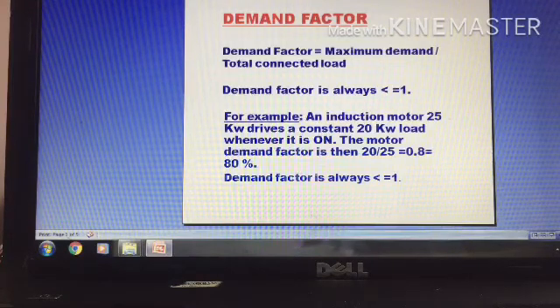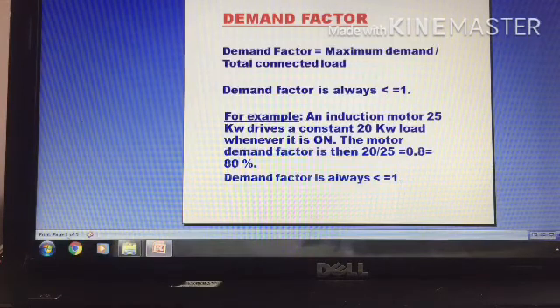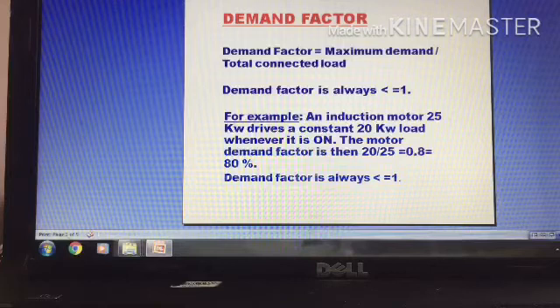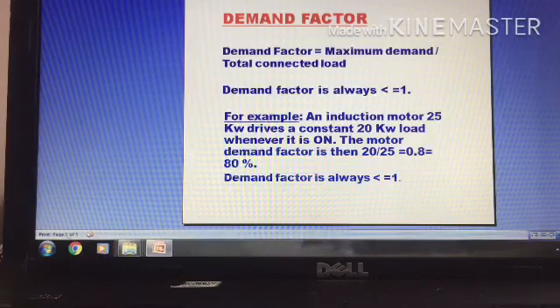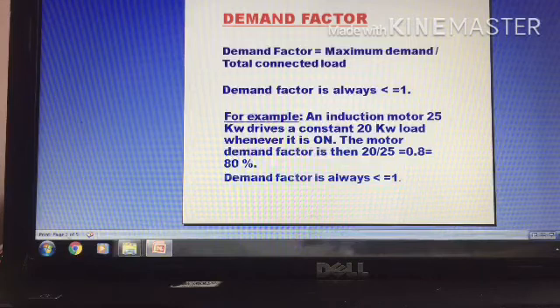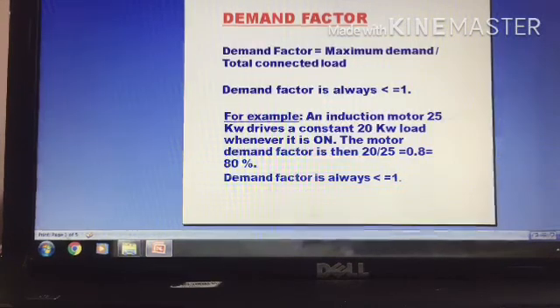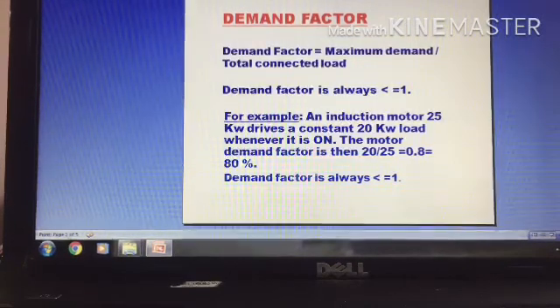Let's look at an example. An induction motor is rated 25 kW, and it draws a load of 20 kW. So the demand factor is 20 divided by 25, which equals 0.8 — that is 80% of the total connected load of 25 kW.